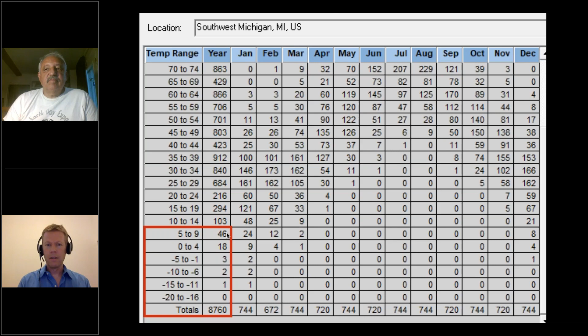Okay, moving on. Especially in heating dominated climates like Michigan, there's a tendency to oversize heat pump systems because in most houses the total or peak heating demand is greater than the cooling demand. And naturally, you want to cover it with a more efficient heat pump rather than relying on electric resistance heat too much. However, an issue with all of the variable speed equipment is that if you oversize too much, the systems during a lot of the year can start short cycling, where the minimum output of these systems is greater than the actual load on the building. And the systems actually have to turn off, and then they turn back on, and then they turn off and they turn on to meet the load. And lab testing from the National Renewable Energy Lab shows that when these kinds of systems are operating in this kind of on and off manner, their efficiency drops by 20 to 40%.